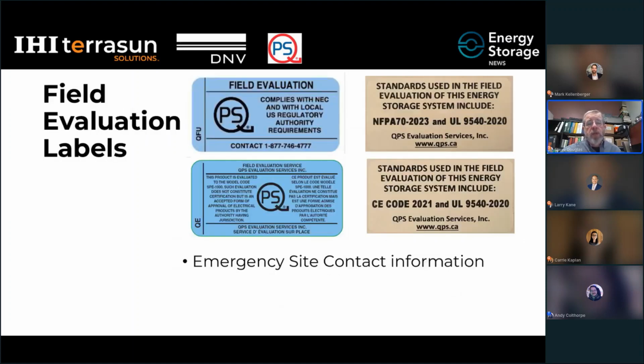On the field evaluation of an energy storage system, I think I'll talk about the differences between certification and field evaluation. On a certification, as I mentioned earlier, the certification organization would allow the manufacturer to put the certification mark on the nameplate for the energy storage system. As part of that process, the certification organization will do a minimum of 4 audits per year on the factory to verify that the energy storage systems that are being manufactured still comply with the report that was created for that specific energy storage system.